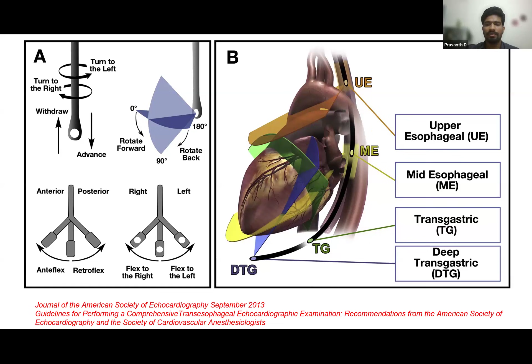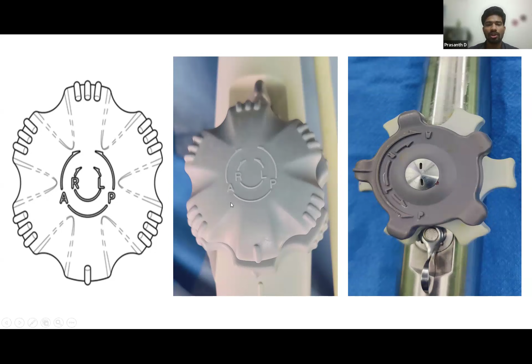In image B, we can see the views of the transesophageal probe, either upper esophageal, mid esophageal, transgastric or deep transgastric. So these are the outer and inner wheels of 2 different TEE probes. The second image is from a GE machine, and the third is from a Philips machine. The indications are like A, P and R, L. So the inner wheel, if you rotate clockwise, will be anteflexing, and if you rotate counterclockwise, the probe tip will go into the retroflex position. Similarly, R and L indicate that clockwise rotation flexes to the right and counterclockwise to the left.